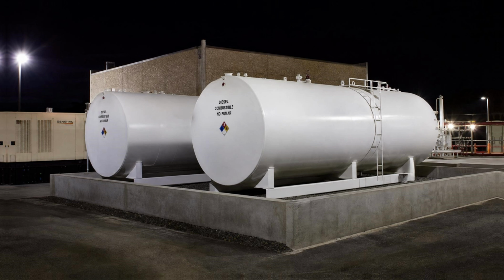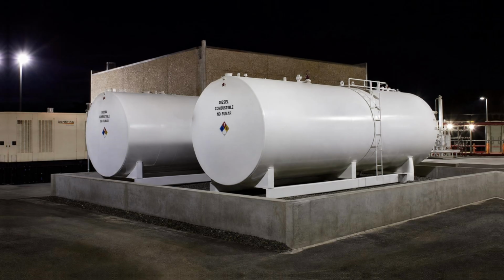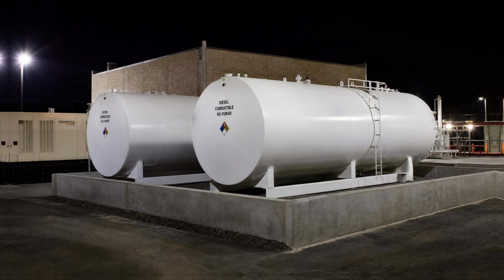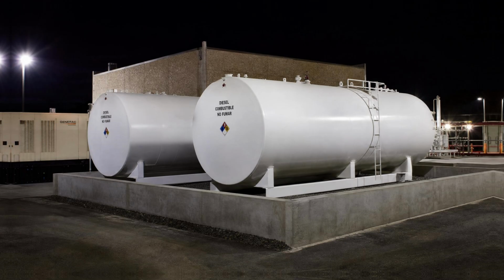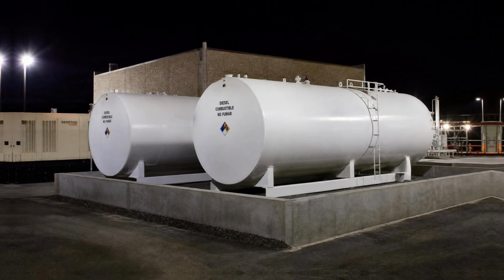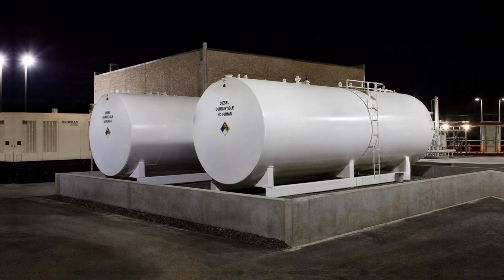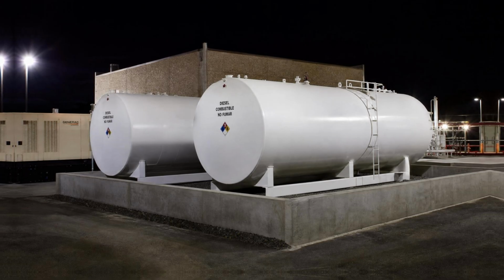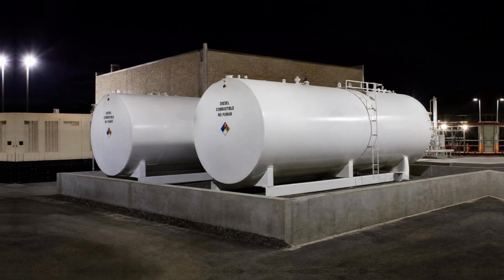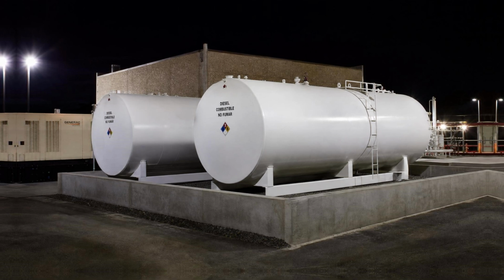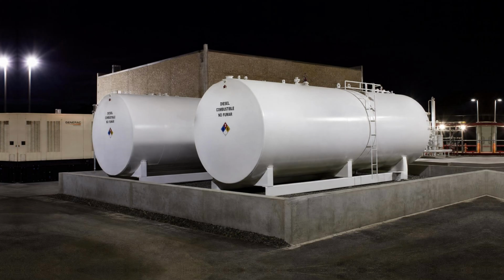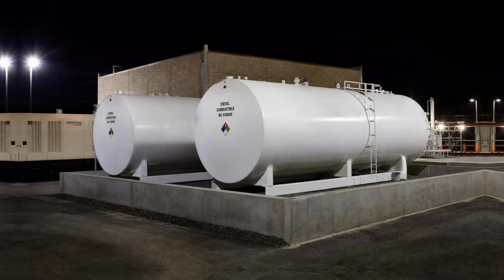The generator room of a large hospital, therefore, may be a substantial space, a purpose-built structure, sometimes located in the basement of the main building, sometimes in a separate generator building on the hospital campus, with room for multiple large generator sets and all their associated fuel, cooling, exhaust, and control systems. It is a warm and mechanical space, full of the careful engineering of systems that are expected to be available at any moment for any duration without advance notice.